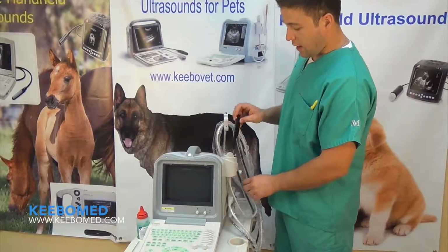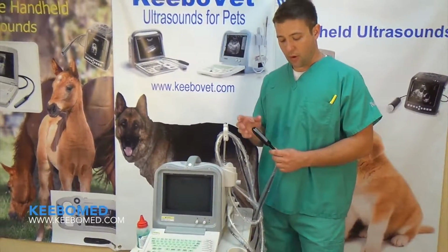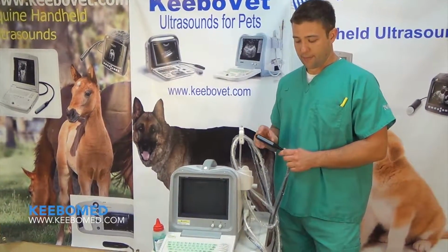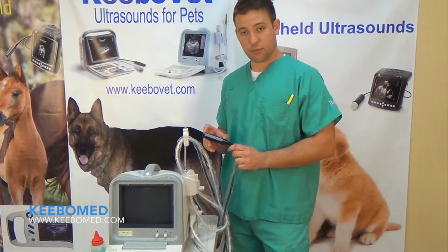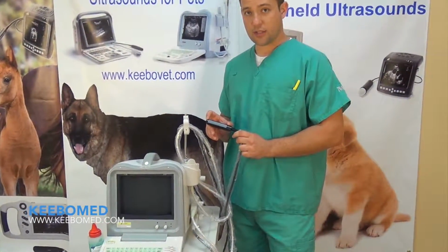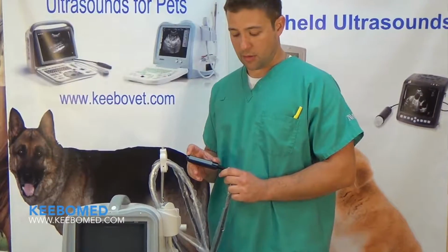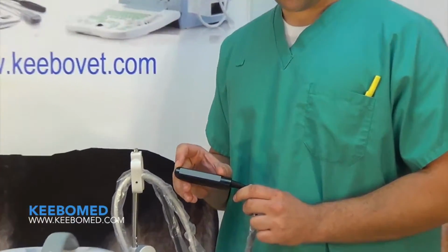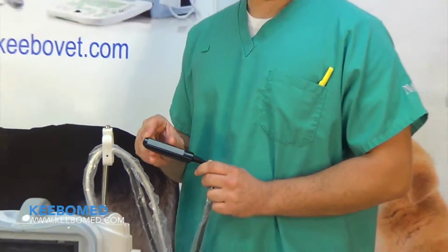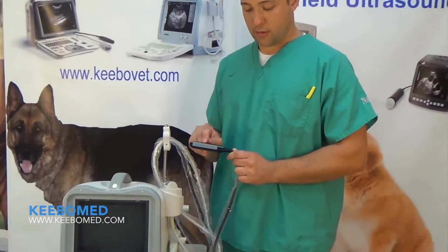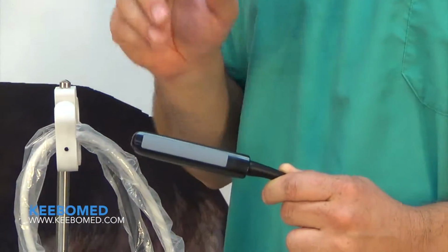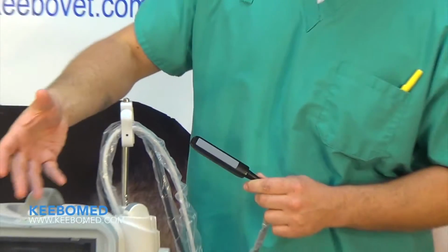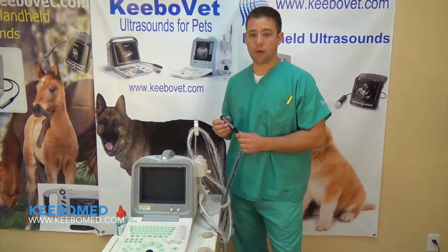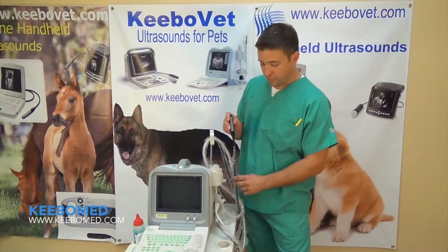Another one, this is a linear probe, also a rectal probe for animals. The face plate here you can see is pretty large. These are 70 millimeters, so 7 centimeters. A lot of the other machines are smaller, and the smaller the field of view, the smaller the image, the less clear. It's just better to have a bigger screen and more imaging. So that's another positive thing about this machine.